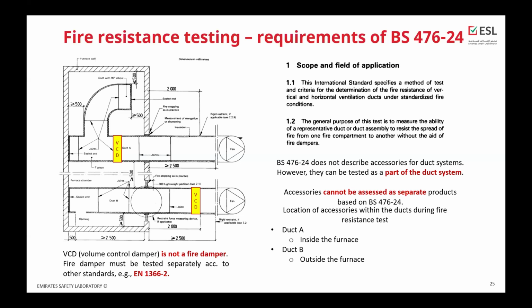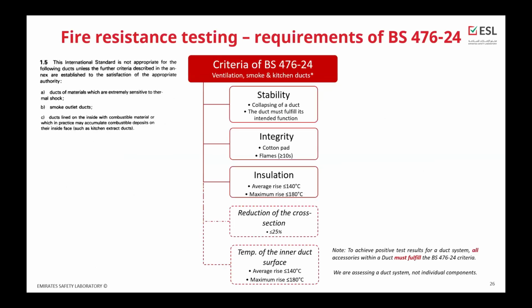And you need to remember that we are talking about the fire duct and accessories to fire duct. The VCD, volume control damper, cannot be a fire damper because fire dampers shall be tested in a separate test under different test standard. You can choose, for example, EN 1366 part 2 to test the fire-rated dampers.